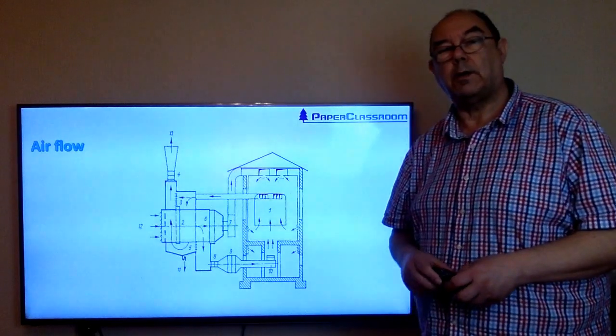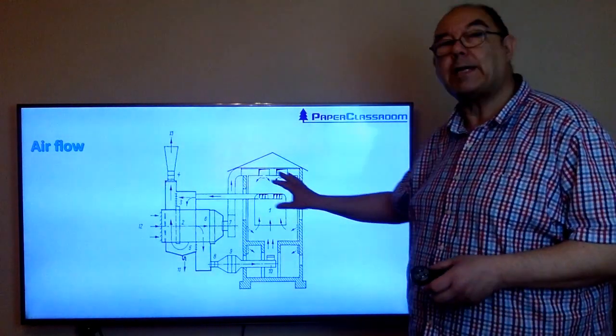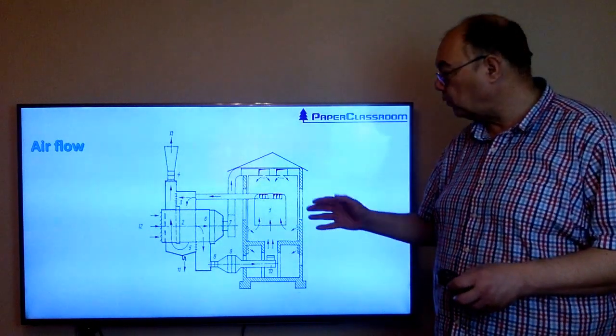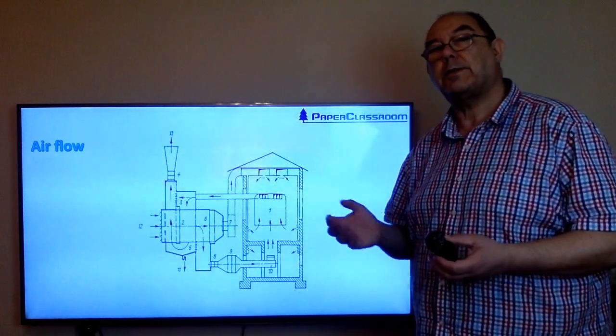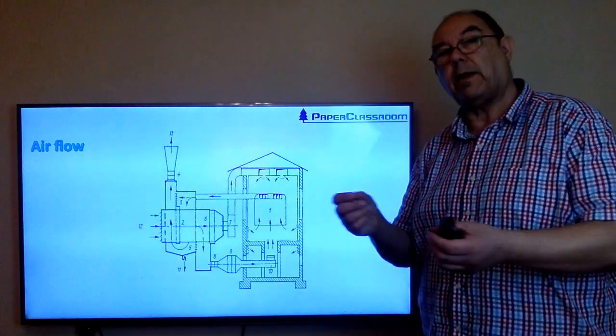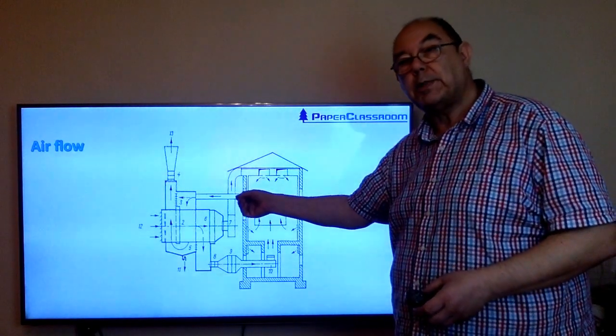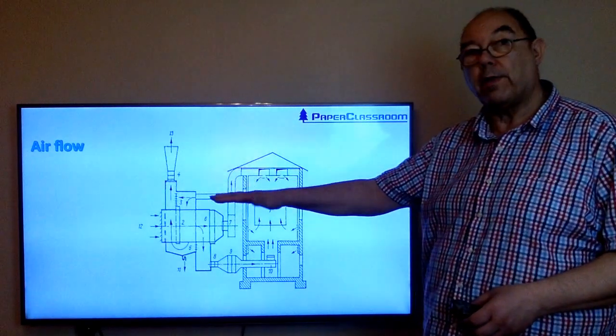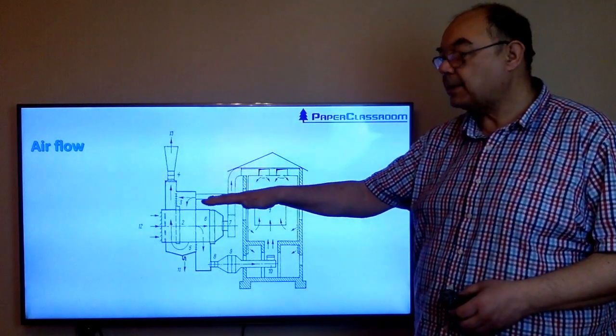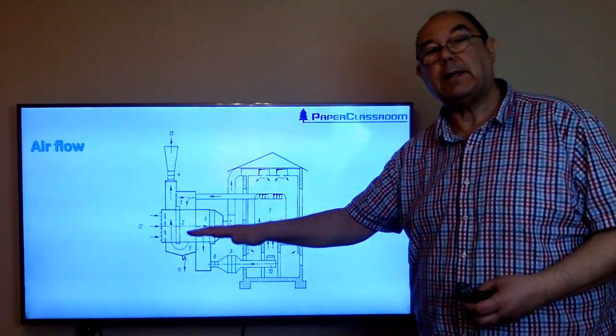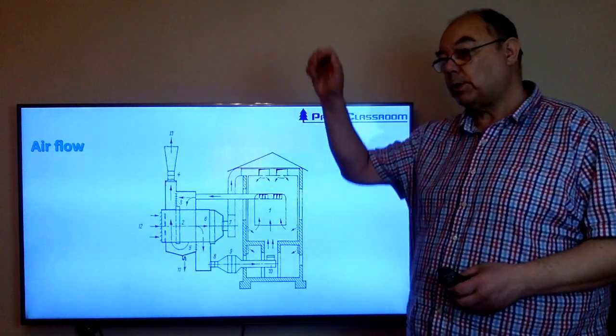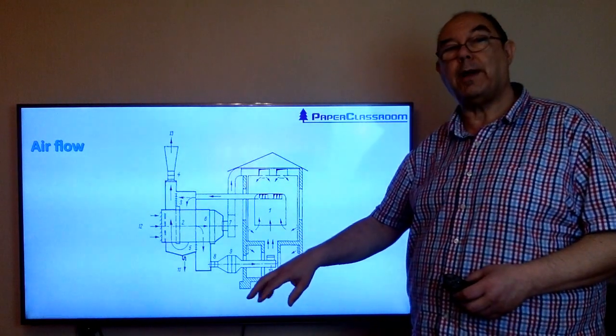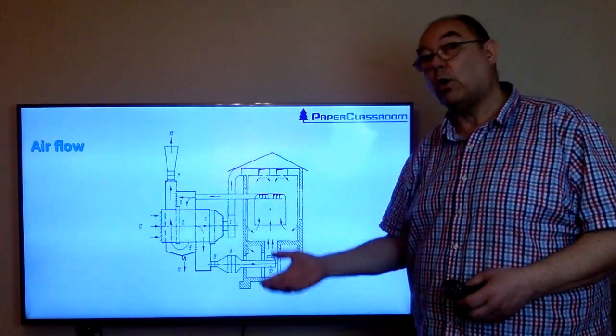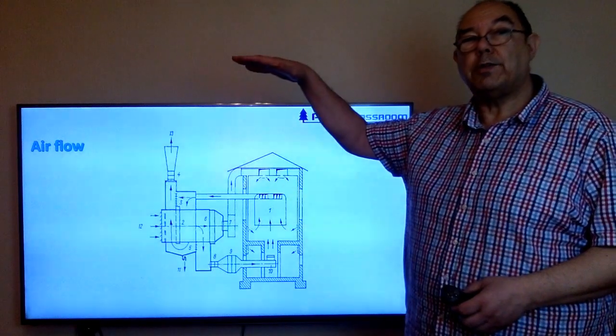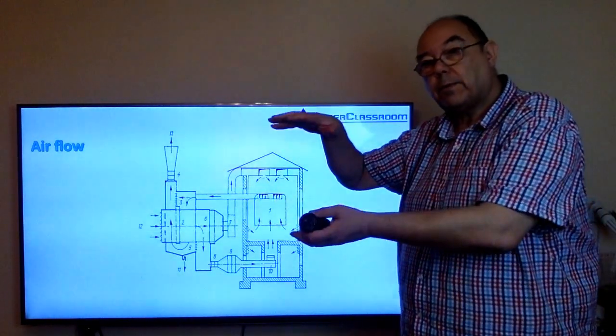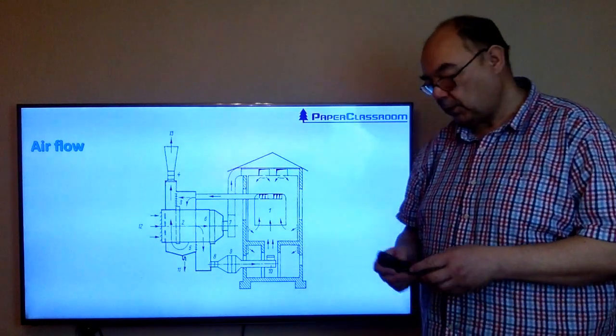And if you go to the experts, the people who monitor and do things like this for a living, they'll take something like a very light piece of cigarette paper and they will put it in the dry system and let go, and it will float there. And that tells them where the 0 point is. If it continues to go down, it's telling them that the airflow downwards is too great. If it goes up, the airflow upwards is too great. If it hovers in the wrong place, the flows are right, but the balance is wrong.